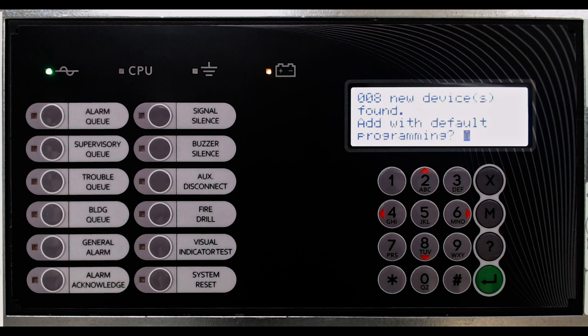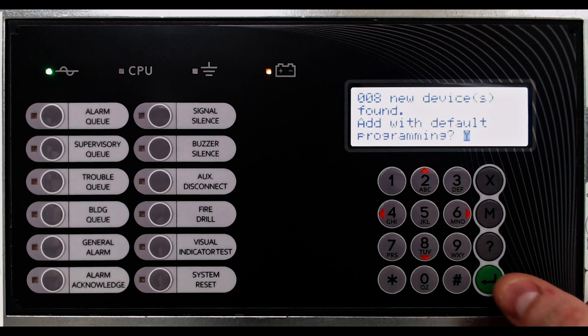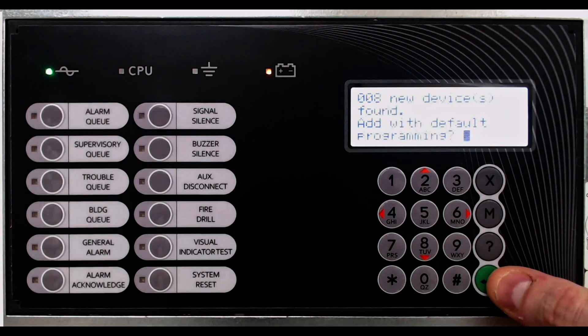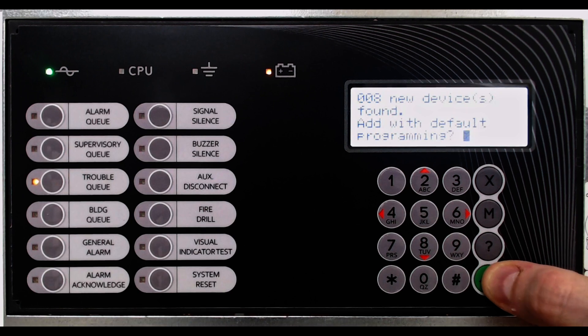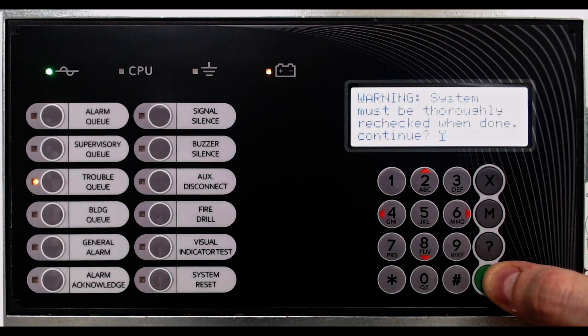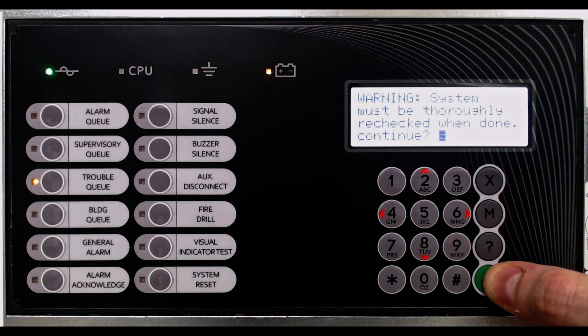All input devices will be set as alarm types and correlated to activate all MACs and supervised output modules. Relay modules are not correlated and require further programming.